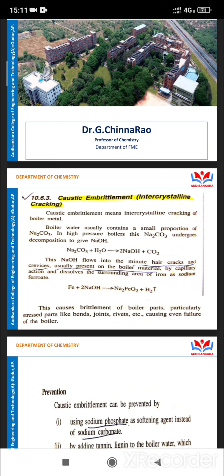This is the main cause of caustic embrittlement or intercrystalline cracking. It mainly happens due to Na2CO3. The Na2CO3 decomposes to NaOH and CO2. This NaOH flows into the minute hair cracks and crevices and travels through them. What happens? They will be damaged, and sodium ferroate is formed. After some time, the indication is embrittlement of boiler parts, particularly stressed parts like bends, joints, rivets, etc., causing even failure of the boiler. This is the caustic embrittlement.